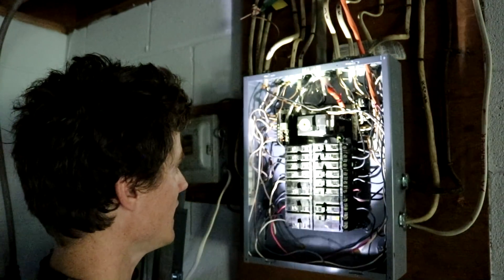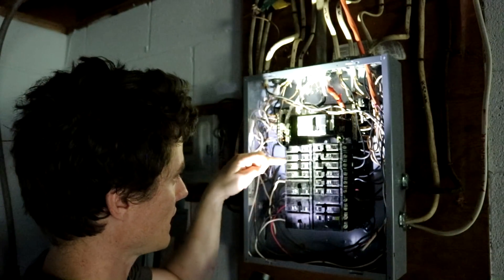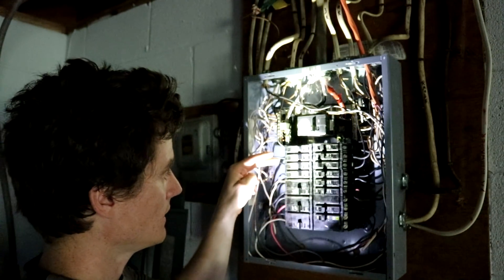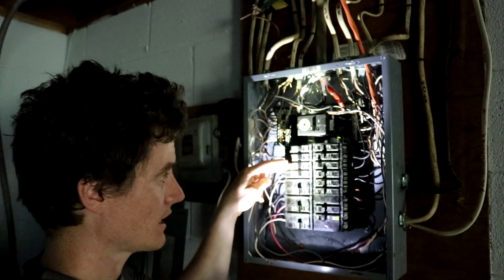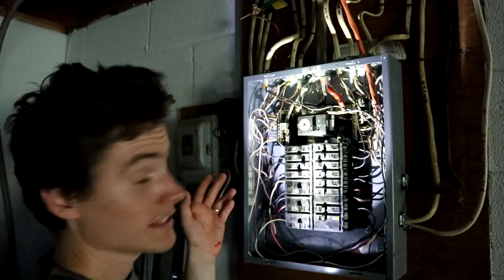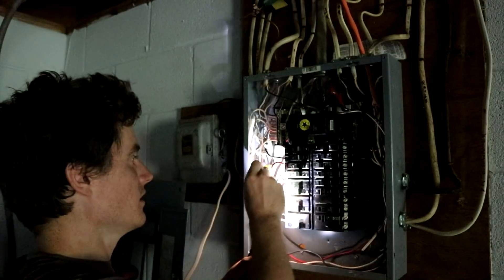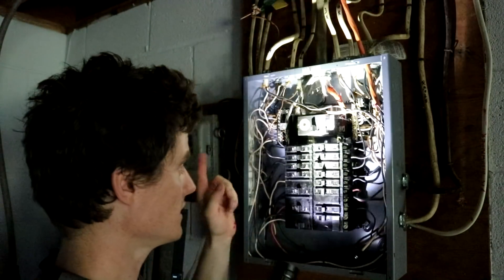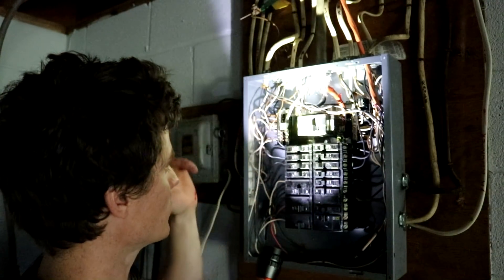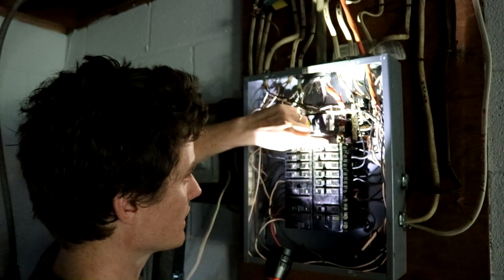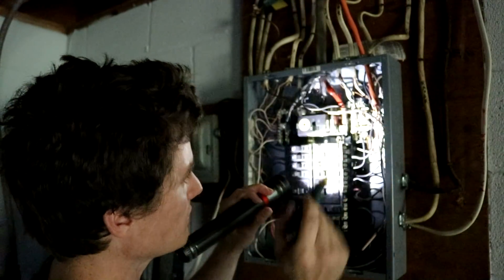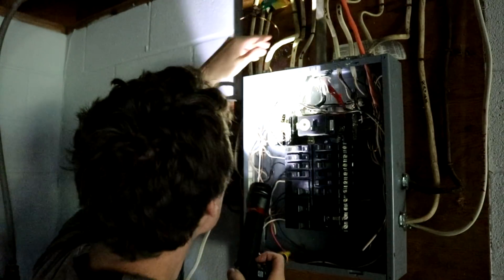So that's turned on, 3R. And then the way this type of a box, this is a QO box, it is putting power to every other breaker. And then the breaker directly to the left or the right of it. So I can turn on this one, for example, the three that's on the left, and that is now putting power to that one. And that particular one is an outlet that is in the bathroom. And again, I said it's every other breaker. So what we are going to do is we're going to skip a breaker. We're going to come up and that is one on the right. We're going to check it. So we've got power coming to it.